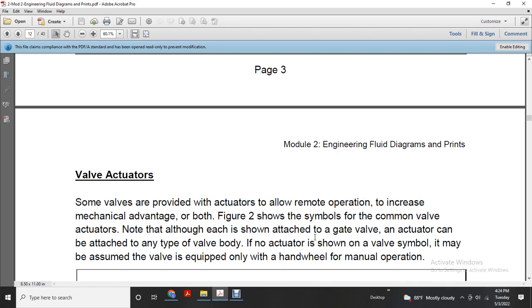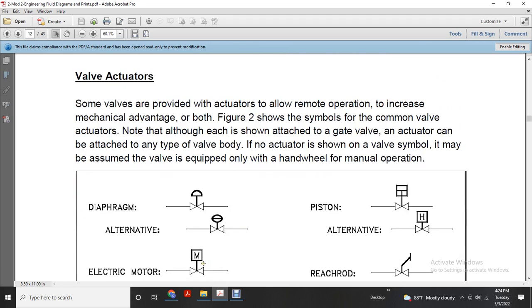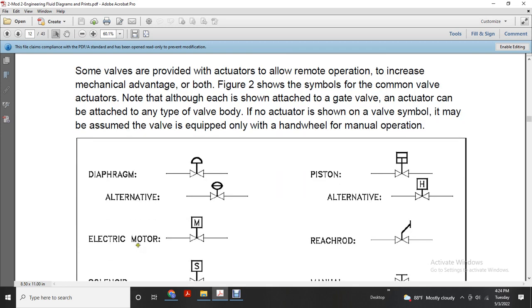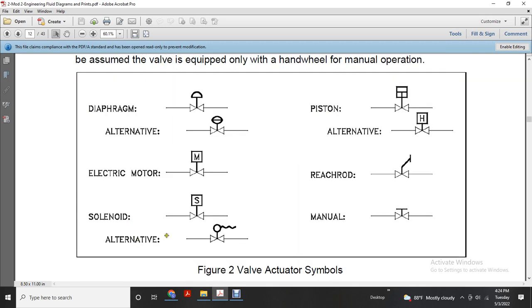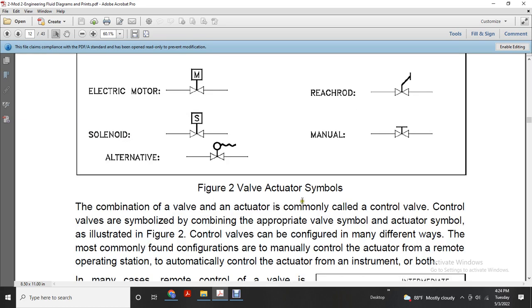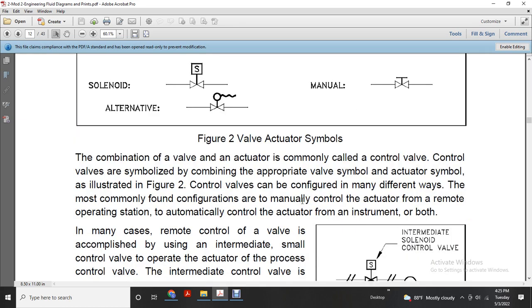Valve actuator. Some valves are provided with an actuator for remote operation or to gain mechanical advantage. Figure 2 shows the symbols for the common valve actuators. Note that each actuator shown attached to a gate valve can be attached to any type of valve body. With no actuator shown on the valve symbol, it may be assumed the valve is equipped with a handwheel for manual operation. So the diaphragm, and all these are gate valves, diaphragm alternative, electric motor, solenoid alternative, piston alternative, rod and manual. The combination of the valve and actuator is commonly called a control valve.